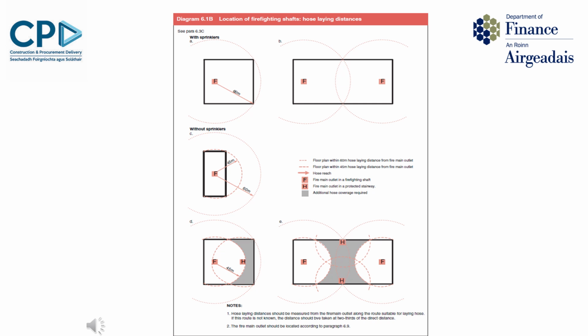This is the new diagram 6.1b that has been added to TBE to illustrate this new requirement. For the top two figures, A and B, where sprinklers are provided, only one criteria applies in that each part of the floor is to be within 60 metres of a fire main in a firefighting shaft. For figure A, one firefighting shaft is sufficient to ensure all parts of the floor are within 60 metres of a fire main. For figure B, because one firefighting shaft does not cover the whole floor, a second firefighting shaft is required to ensure all parts of the floor are within 60 metres of a fire main in a firefighting shaft.